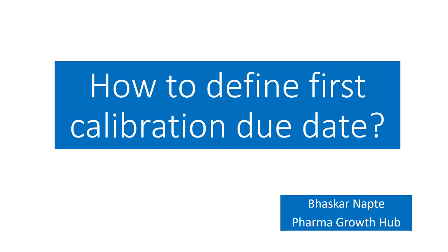As part of your quality system, you complete the qualification of the instrument or equipment, design the SOP for the same — both for operation and calibration. And once the SOP gets effective, you conduct the calibration of the instrument.